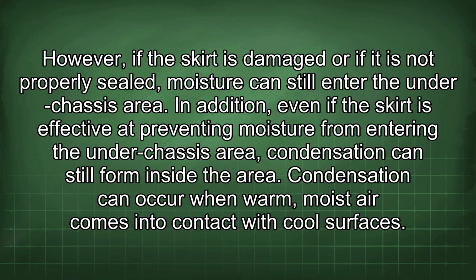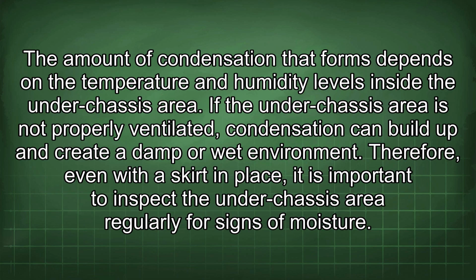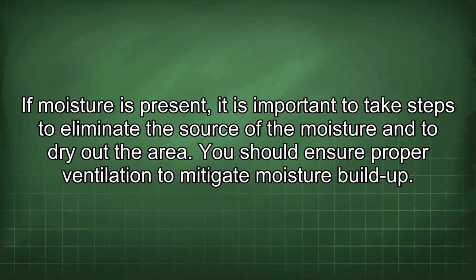In addition, even if the skirt is effective at preventing moisture from entering the under-chassis area, condensation can still form inside the area. Condensation can occur when warm, moist air comes into contact with cool surfaces. The amount of condensation that forms depends on the temperature and humidity levels inside the under-chassis area. If the under-chassis area is not properly ventilated, condensation can build up and create a damp or wet environment. Therefore, even with a skirt in place, it is important to inspect the under-chassis area regularly for signs of moisture. If moisture is present, it is important to take steps to eliminate the source of the moisture and to dry out the area. You should ensure proper ventilation to mitigate moisture build-up.